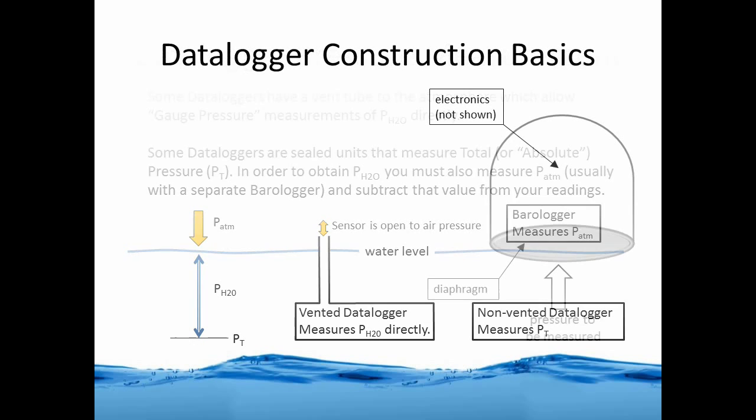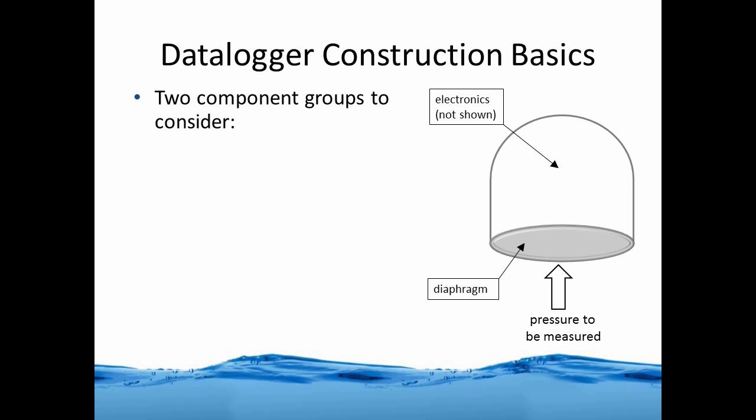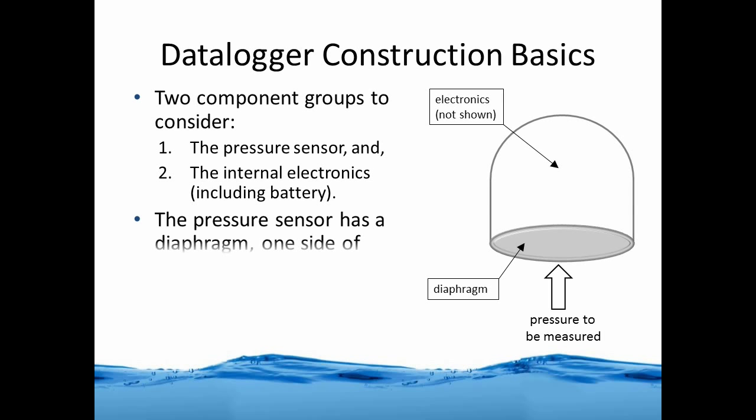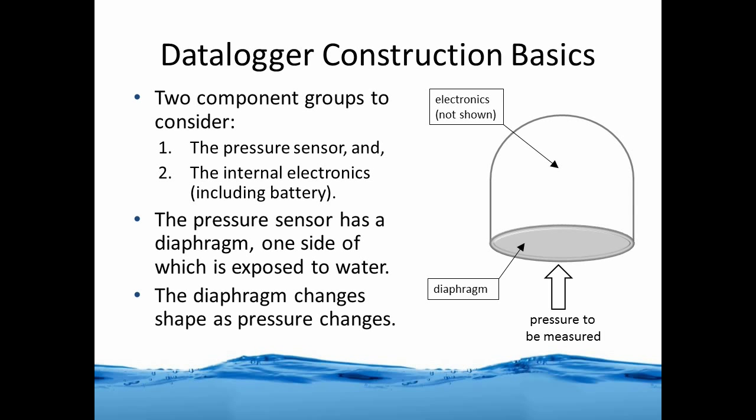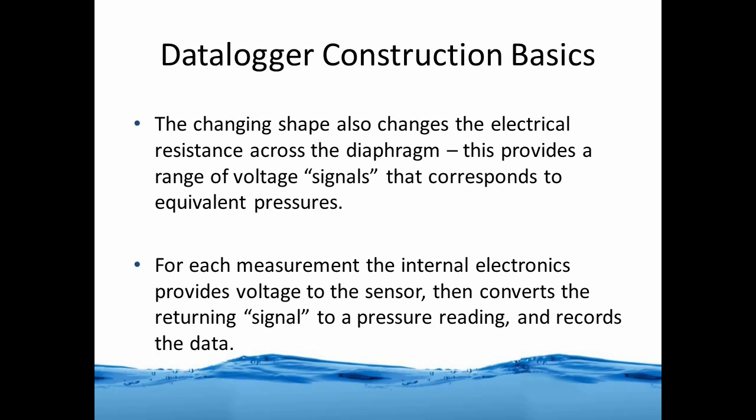Let's look at some data logger construction basics. Data loggers essentially have two components: first, the pressure sensor, and secondly, the internal electronics that include a battery. The pressure sensor has a diaphragm; one side is exposed to the water, and the diaphragm changes its shape as the pressure changes against it. The changing shape also changes the electrical resistance across the diaphragm — some refer to this as a bridge circuit. This provides a range of voltage signals that correspond to equivalent pressure readings. For each measurement, the internal electronics provides voltage to the sensor, then converts the returning signal to a pressure reading and records the data.